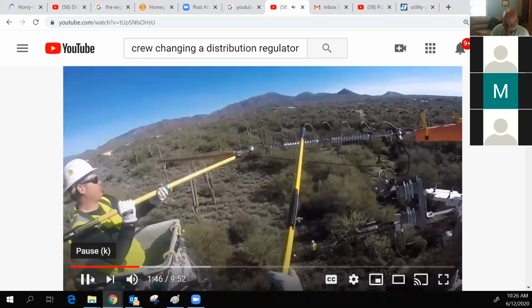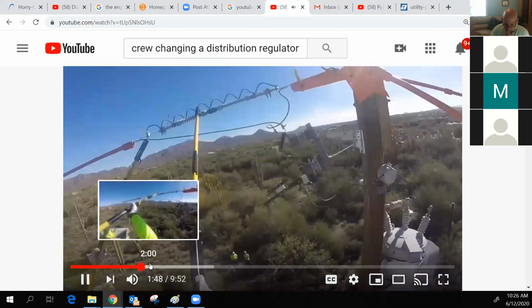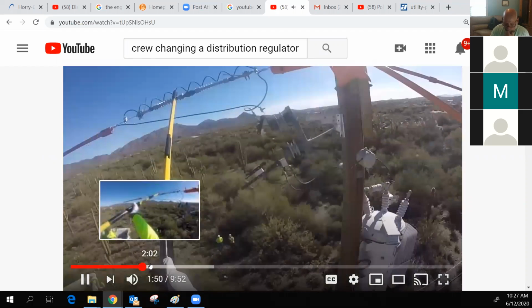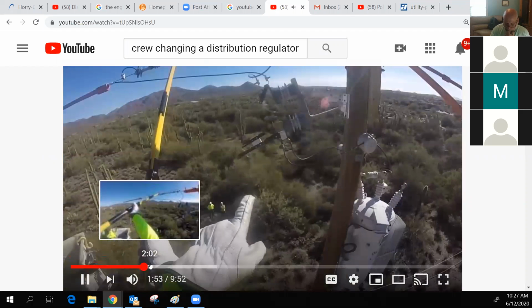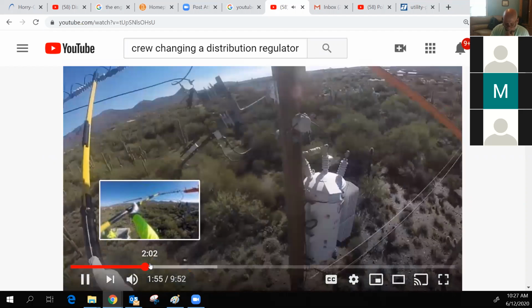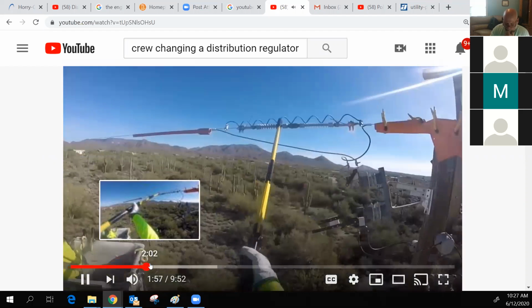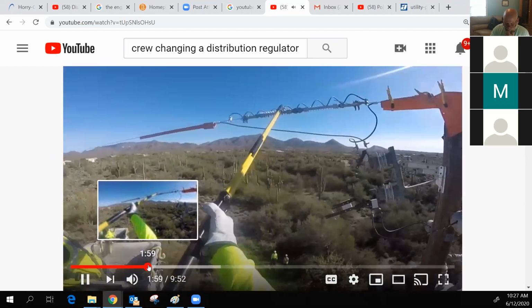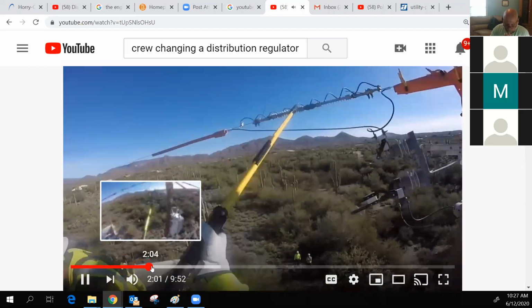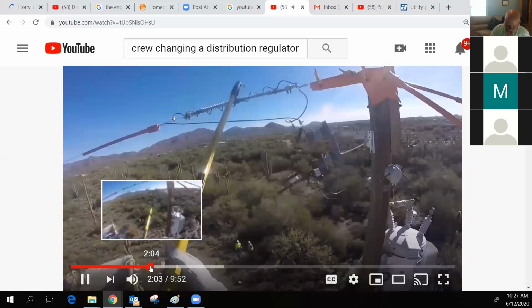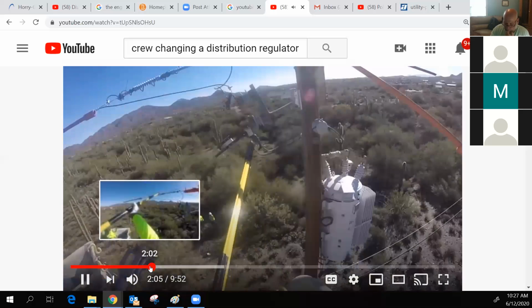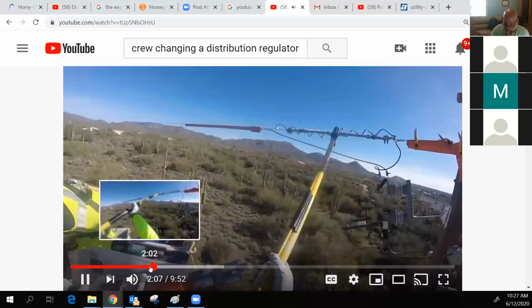The reason you don't want to put this on with the switch closed in is because when the regulator's online, you'll get circulating current. Right now the regulator is offline, as you can see, so we don't have to worry about that.